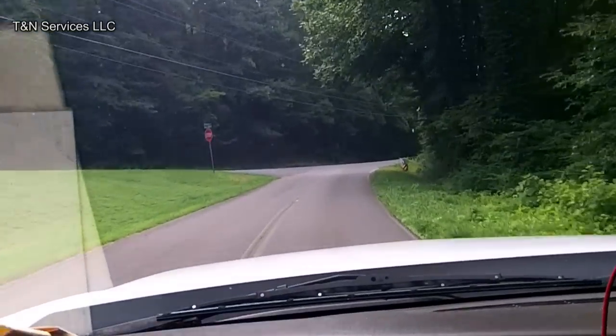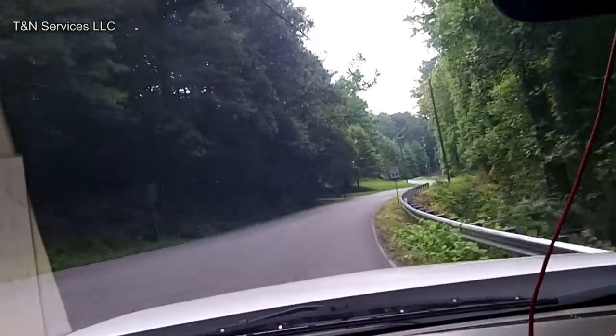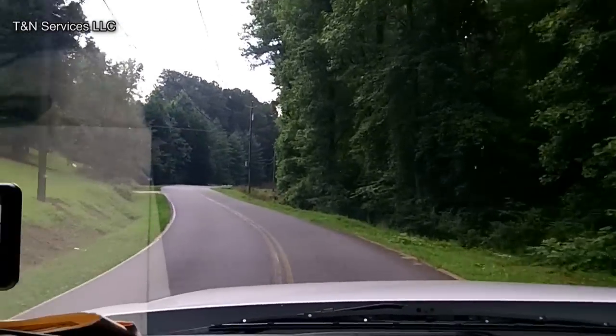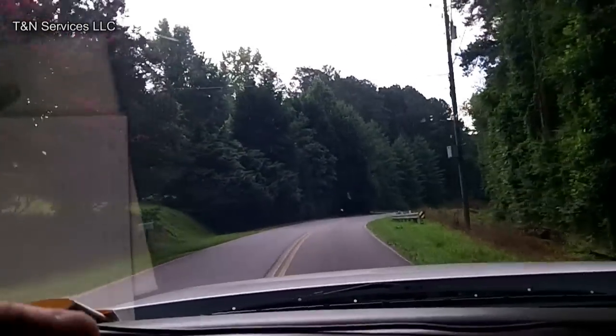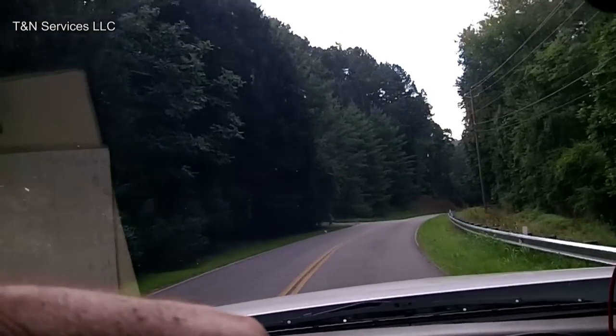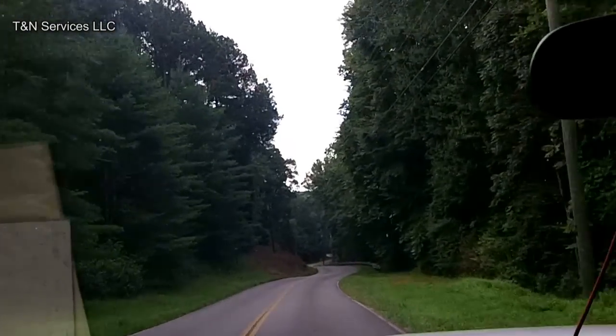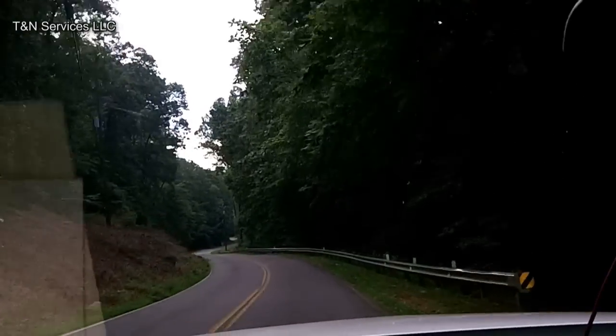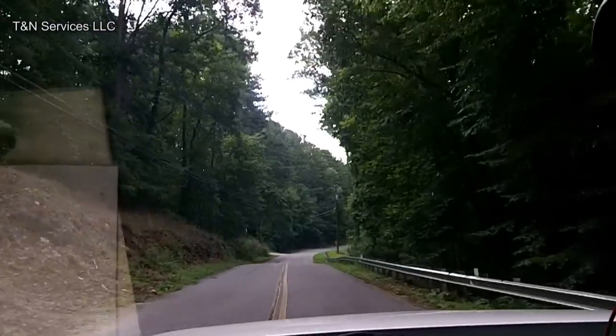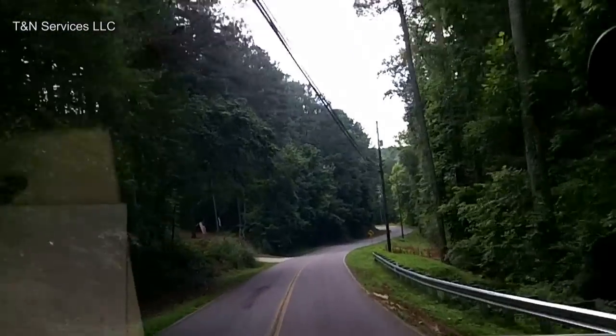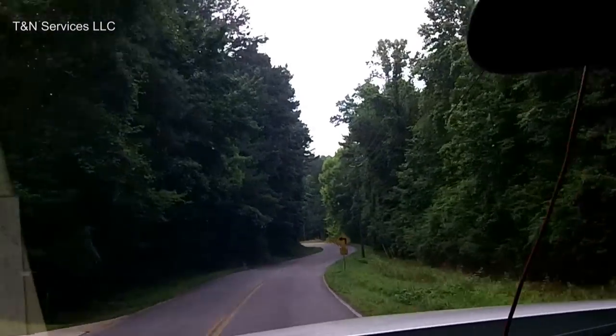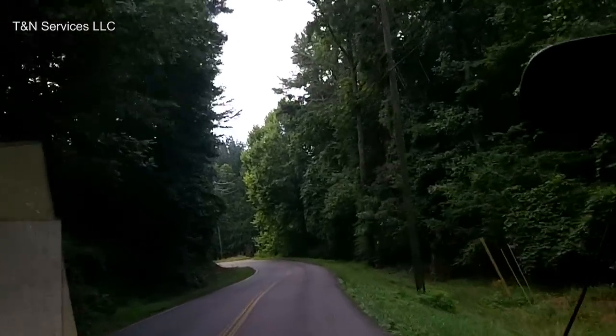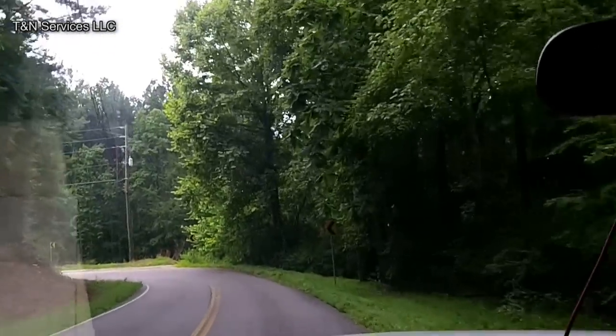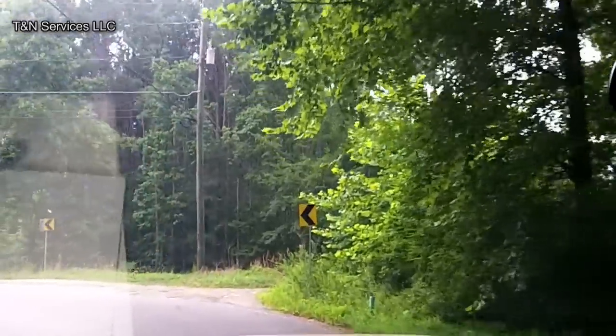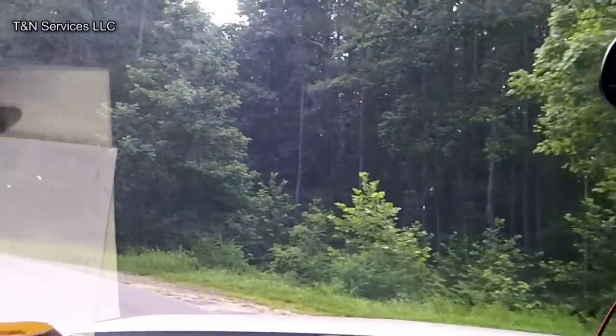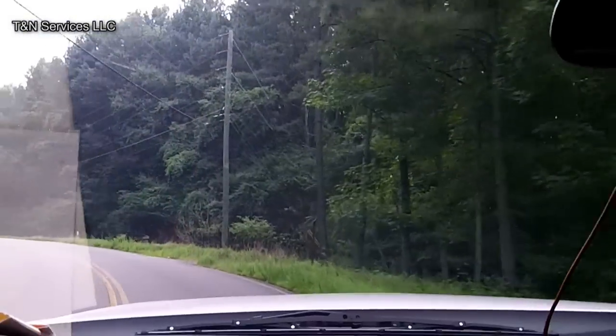Today is July the 29th. She called and said it's not cooling. She called me about 8:30 and I said I'll be over there in about 10 minutes. This is very unusual for me, most of the time I'm not working 10 minutes away from my house, I'm working 45. So it's a treat this morning to drive 10 minutes to my job. So anyway, I get there, the unit's frozen up, the heat pump. I throw it in heat, put my gauges on the common suction port and the liquid side, and it's running 100 pound suction and a 400 head, and I knew right then I had a problem.